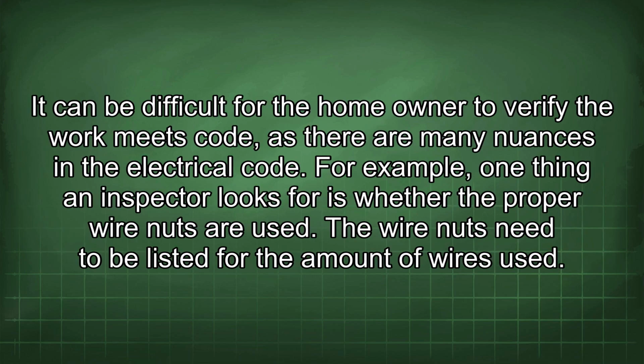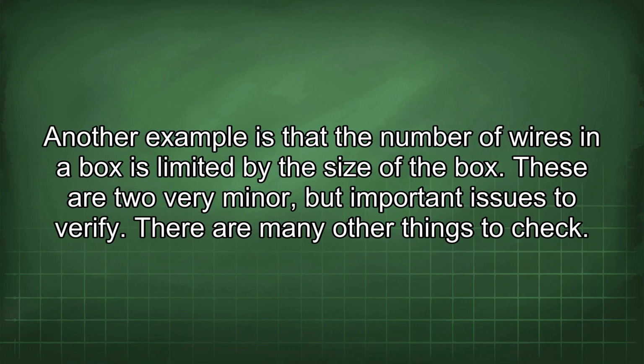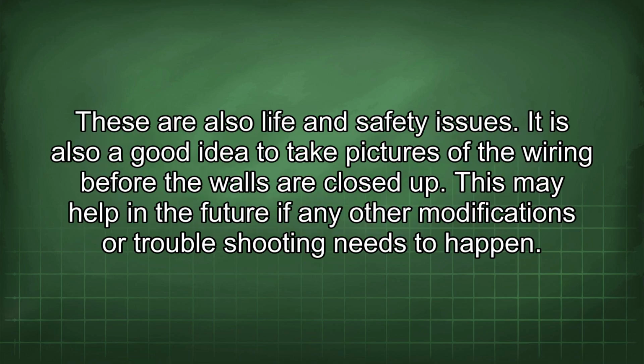It can be difficult for the homeowner to verify the work meets code, as there are many nuances in the electrical code. For example, one thing an inspector looks for is whether the proper wire nuts are used. The wire nuts need to be listed for the amount of wires used. Another example is that the number of wires in a box is limited by the size of the box. These are two very minor, but important issues to verify. There are many other things to check. These are also life and safety issues. It is also a good idea to take pictures of the wiring before the walls are closed up.